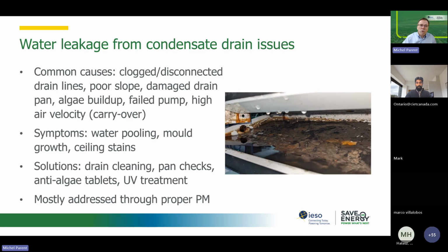It does not do anything for virus. It's about eliminating mold growth, and making sure that the velocity is not too high. Sometimes there's a restriction that will make the velocity through your cooling coil too high, and it will carry over the condensate, which can accumulate on the air handling unit floor and create mold issues. So there are different things that need to be verified.